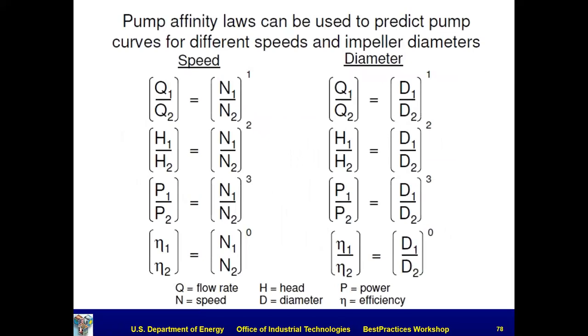Let's go on to the affinity laws. Okay, so we talk about the fan affinity laws and the pump affinity laws. The appropriate use of these is to predict changes in pump curves, not operating points. These modify the pump curve or the fan curve, and where it operates is at the intersection of the modified pump or fan curve and the system curve, because the shape of the system curve affects the outcome in terms of operating points. So it's not just affinity laws, okay?